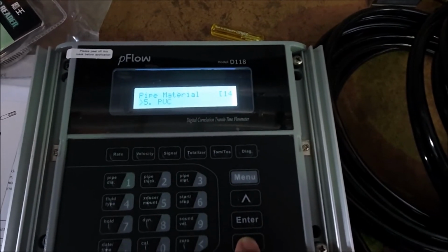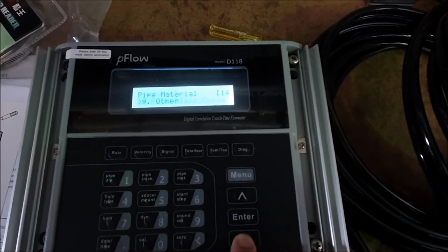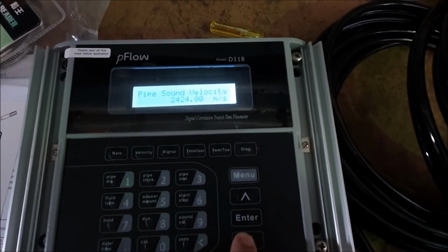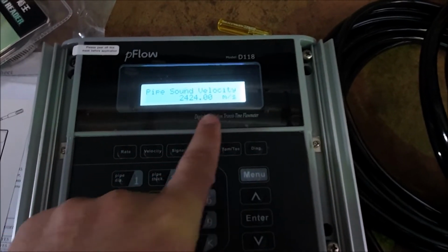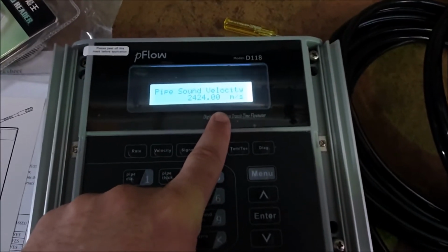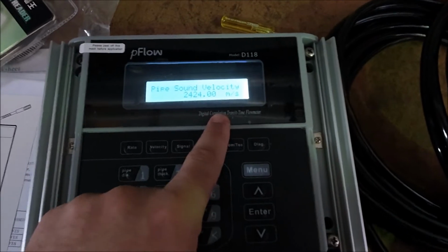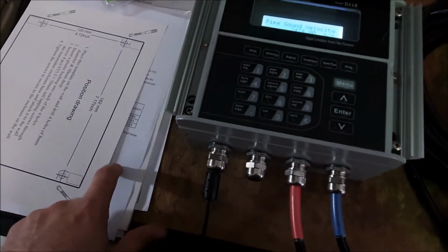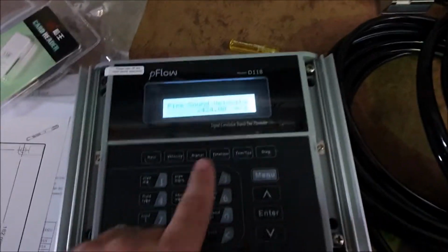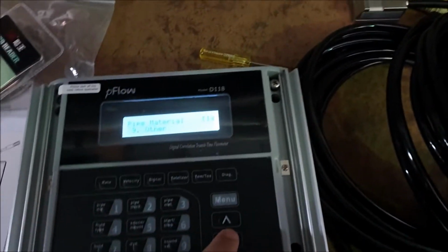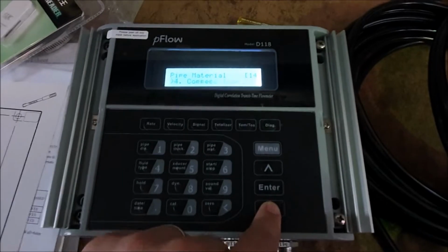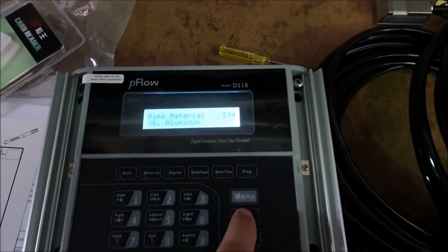If your pipe material isn't listed, just select other, then go down a menu, and you can manually enter the sound speed of your pipe. You might find that online, or there are a couple others in the back of the manual. It just needs to know the sound speed of your pipe, using these known sound speeds. We'll set this one as PVC, which is what I'm using.